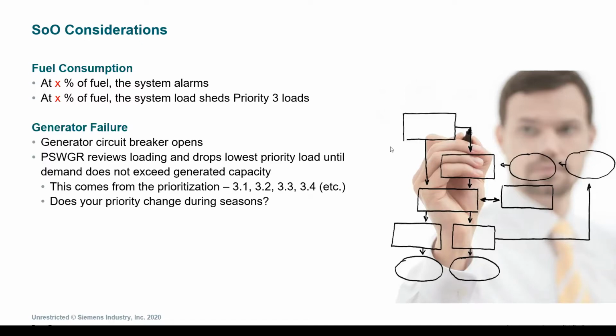From a generator failure, we'll touch on in a few minutes some of the failure modes, but when a generator fails, the generator circuit breaker opens, the parallel switchgear reviews the load, and then drops the lowest priority until that demand, again, does not exceed that generator capacity. This comes from the prioritization of the transfer switches that we'll get into in a few minutes.